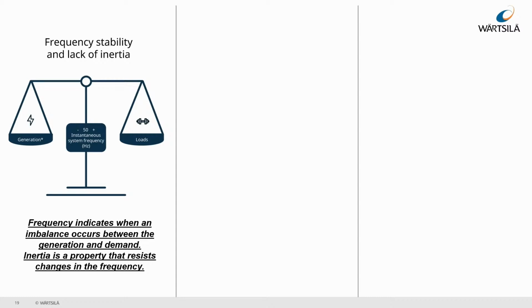Frequency stability is about the balance of load and generation in the power system, and it indicates if there is an imbalance. Inertia is a property that helps resist changes in frequency. This means that if there is a load change, the frequency will move slowly and you have time to react. Taking away the inertia, you have less time to react, and you need much faster controllers for that.